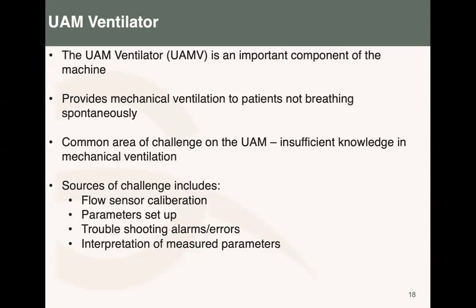On flow sensor calibration, this actually comes in two ways. Some is real calibration, but some users, when told to do the machine check, go straight to the flow calibration. Flow calibration is actually part of the machine check, not the machine check itself. I've been to places where every time we discuss and say, let's go through the machine check, people go straight to calibration. This is important to do, but it should be done as part of the machine check, not just done alone and then assume the machine is okay.